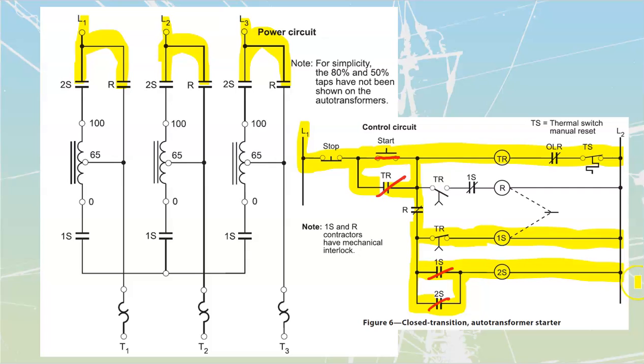What does that do on our starter? Well, let's start by following these through in the order that they closed. The first one that closed was the 1S. We saw that the 1S closed first. That's this one here. That 1S closure is simply going to create a Y type of connection. It closes in the coils of all of these over here. We saw that the 1S, when it closed, closed in the 2S as well. And as soon as we've closed in the 2S over here, that is going to apply power all the way through down to this Y point.